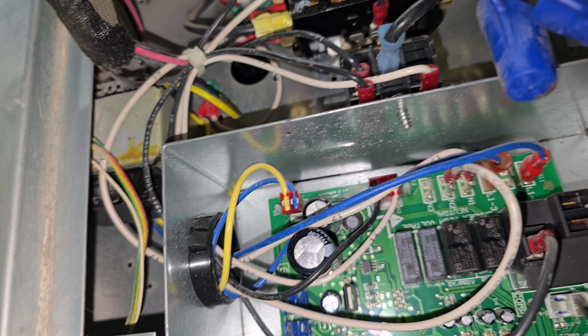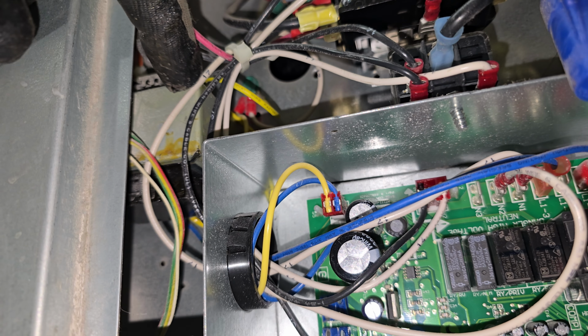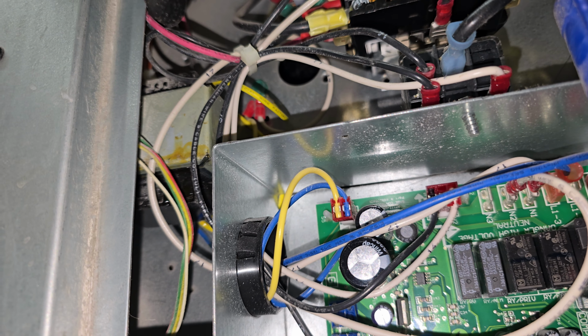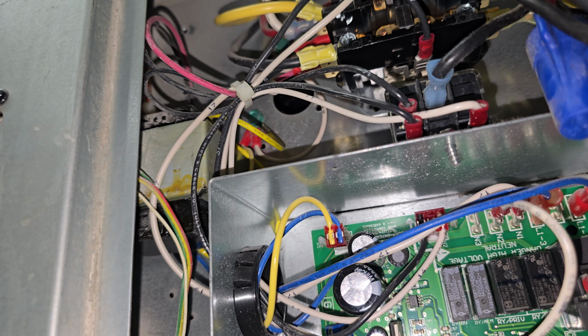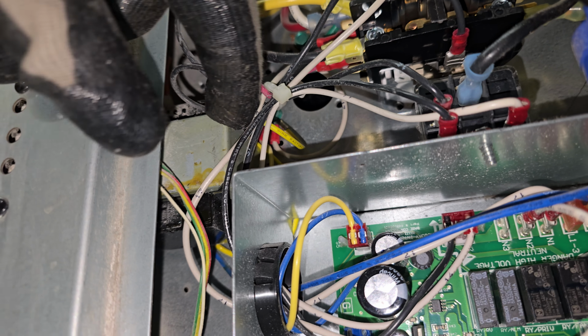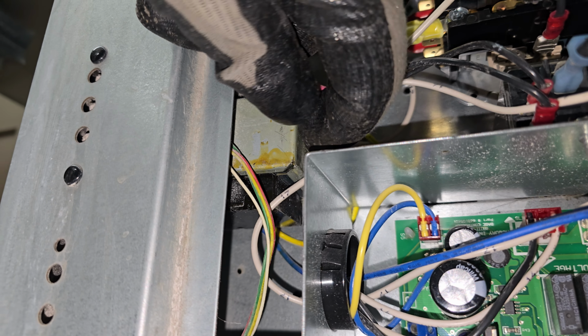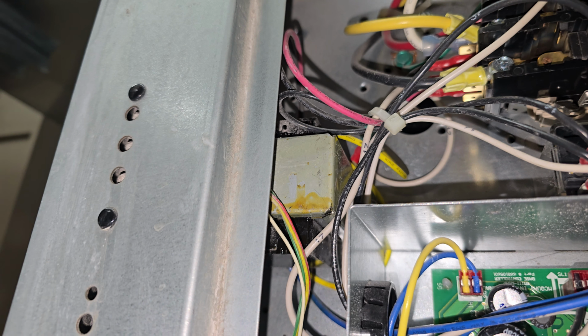and again I have to check my transformer because my compressor is very hot. My transformer is on 208 or 230. So I'm going to see what voltage the building has and what voltage this unit has. I want to see what my transformer is giving out. Is it giving out 208 or 230?